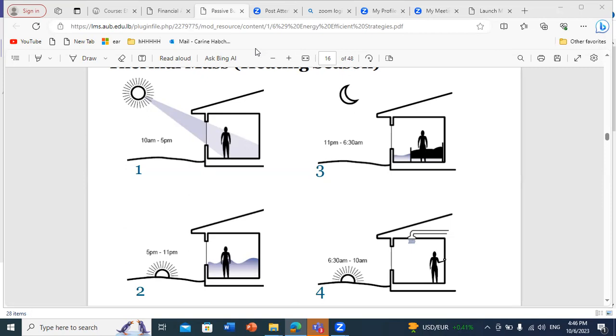With time this temperature difference will decrease because the thermal mass is giving away energy. So the temperature of the thermal mass will decrease until at a certain stage of equilibrium, where the temperature of the thermal mass equals the temperature within the space, and you will not have any more release of heat to the room. This will happen nearly around 6:30 a.m.